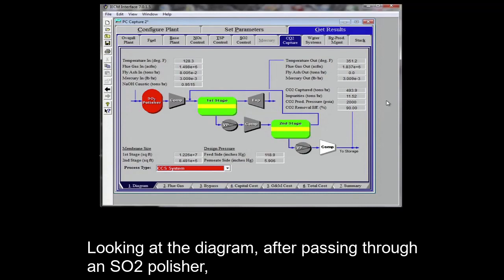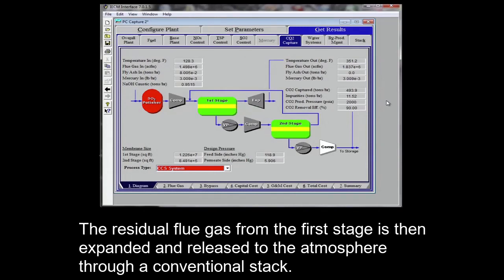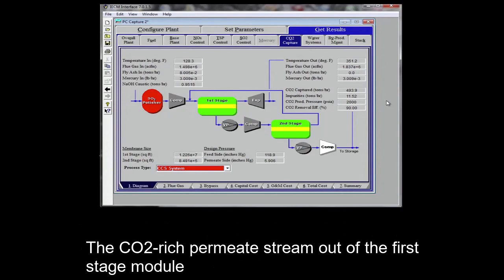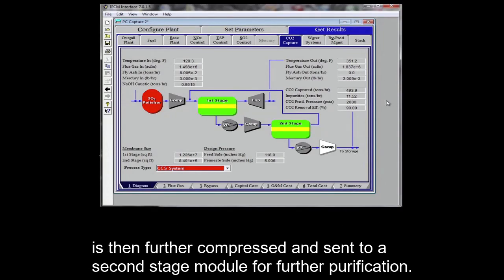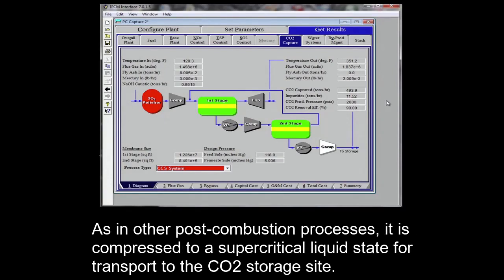Looking at the diagram, after passing through an SO2 polisher, flue gas is compressed to a high pressure before entering the first membrane stage. The residual flue gas from the first stage is then expanded and released to the atmosphere through a conventional stack. The CO2 rich permeate stream out of the first stage module is then further compressed and sent to a second stage module for further purification. The permeate stream from the second stage membrane module is the final stream of captured CO2. As in other post-combustion processes, it is compressed to a supercritical liquid state for transport to the CO2 storage site.